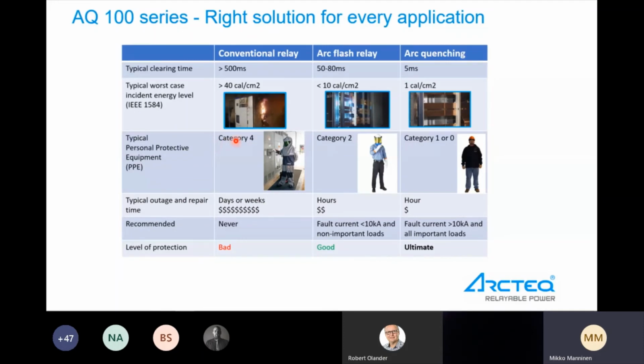And the IEEE committee had this new standard in 2018 for the new calculation methods, and they spent 16 years and made 1200 explosive arc flash tests. So it is quite time consuming to do such testing. But with arc flash relays we can already go to a good level, and with arc quenching to the best category level. So this is the ultimate solution, this arc quenching.